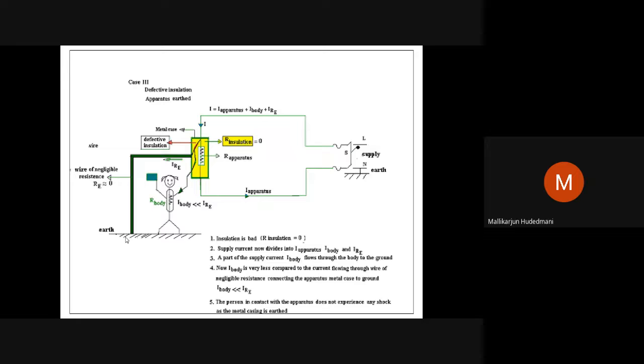Then, even though the equipment is faulty, the earth pin is provided with a wire. When a human touches it, the path for the current is 2. One is a low resistive path to the earth pit and the other is a resistive path through the human body. The human body experiences comfort now because only a minor milliampere is flowing, if at all. Otherwise, every ampere will rush through the low resistive wire to the earth.